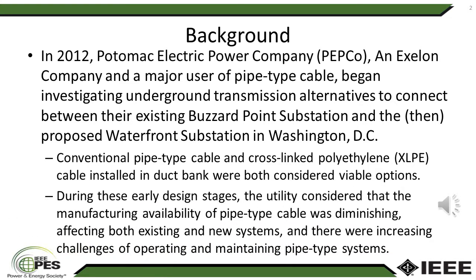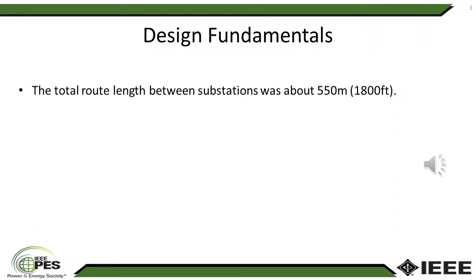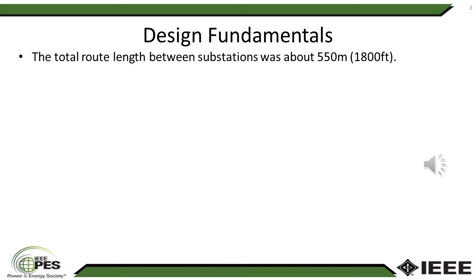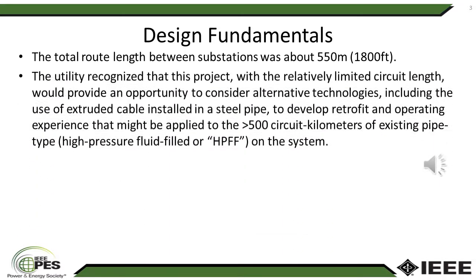During these early design stages, the utility also realized that manufacturing availability for pipe-type cables was diminishing in the industry, and that operating and maintaining these systems was increasingly becoming a challenge. The proposed new substation was approximately 550 meters, or 1,800 feet from the existing substation. The utility realized that this relatively short circuit length would allow an opportunity to investigate alternatives for retrofitting into a steel pipe, which would allow later servicing of their existing 500 circuit kilometers of existing pipe-type circuits.